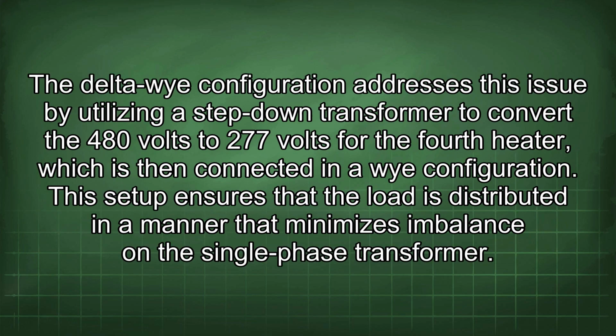The Delta-Wye configuration addresses this issue by utilizing a step-down transformer to convert the 480 volts to 277 volts for the 4th heater, which is then connected in a Y configuration. This setup ensures that the load is distributed in a manner that minimizes imbalance in the single-phase transformer.